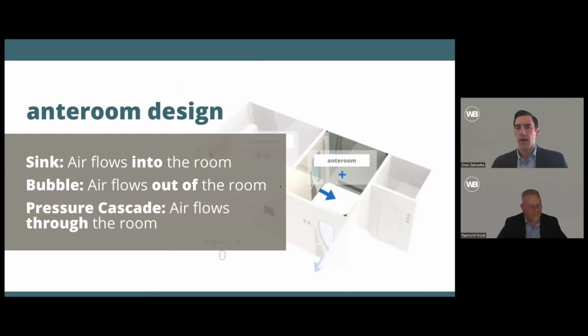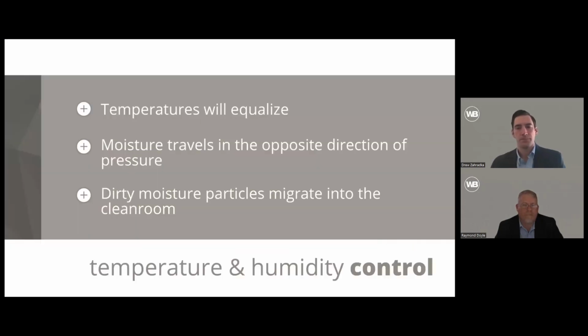So a standard pressure cascade is when the air flows in through the room and then out through the other door. Your sink is when that room is completely exhausted and air will come from the clean room and from the adjacent dirty corridor into the anteroom and then get exhausted out. And then a bubble is when you pressurize your anteroom so that nothing can flow into the anteroom from the dirty corridor and nothing flows into the anteroom from your clean room.